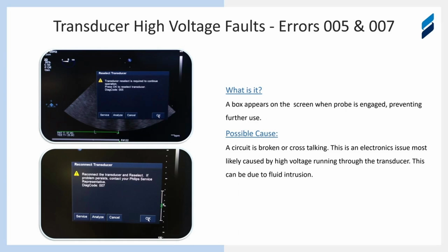So the one thing to really be careful around these types of failures is the idea that because it's a high voltage line, this can actually go damage the ultrasound system itself. So when the probe is shorting on its own, it actually can cause a short all the way through that transducer select port into those high voltage boards, in this particular case an acquisition module, and cause damage. And so this is why it's so important on these specific high voltage failures, pull that transducer from service as quickly as you can, because the longer you try to use it, the more vulnerable that system is to actually suffering also from this short in the acquisition module, which ends up frying your acquisition module as well.